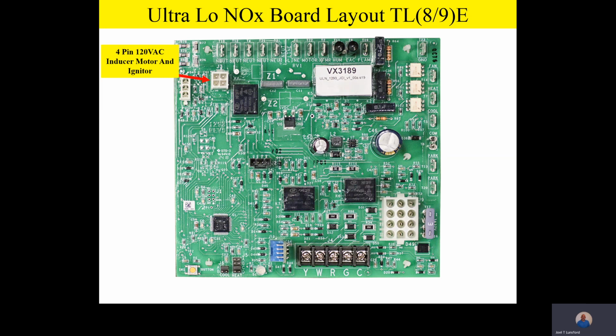Right up next to the 4-pin plug, we see we've got 5 neutral connections. Those 5 neutral connections will have the white wires from the different components on there. So this is 120 volt neutral connections, and there's 5 of them as you take a look at the board. Right next to the neutral bus, we see that we have a 120 volt input to the board. Now this is where the power comes into the board to drive the 120 volt components.